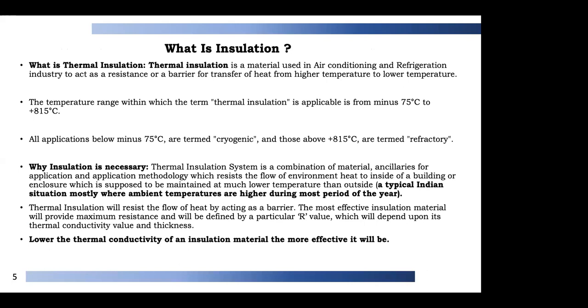Thermal insulation is a material used in air conditioning and refrigeration industry to act as a resistance or barrier for transfer of heat from high temperature to lower temperature. The temperature range considered as thermal insulation is from minus 75 degrees to plus 815 degrees centigrade. Below minus 75 degrees is considered cryogenic, and above 815 degrees is considered refractory.